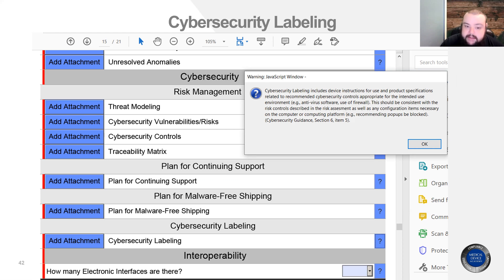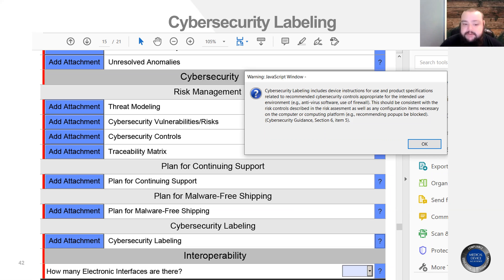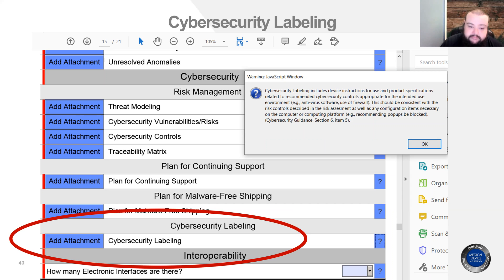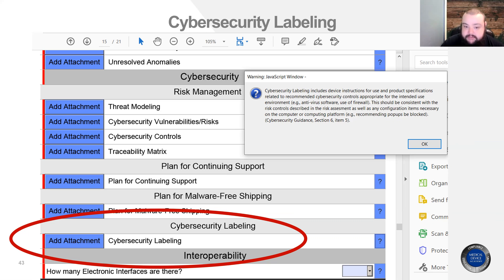We've covered a lot of broad things about labeling, but we don't have a great itemized list of the exact documents the FDA wants to see. What's on screen now is a screenshot from the FDA's E-STAR submission process, and I did an A-B comparison for the E-STAR submissions they have open. Cybersecurity labeling is identical both for medical devices and in vitro diagnostic devices — this section on both E-STAR applications is identical.